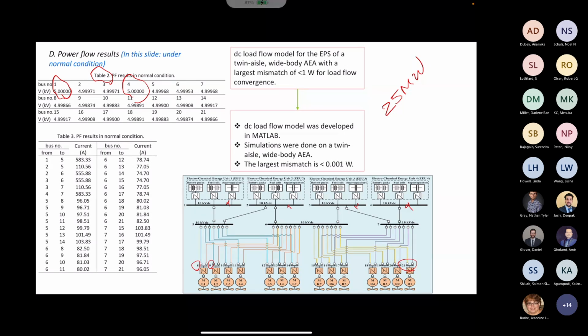I'm not going to the design of the cable at this time, I'm just considering a 10% wiggle room between what you have on the data sheet and what you get from the load flow. For the normal load flow, if you go to table 2, you see that you don't have that much voltage drop. In a power system, we know you're allowed to have 5% below and higher, here you see all the voltages are very close to that 5 kV.